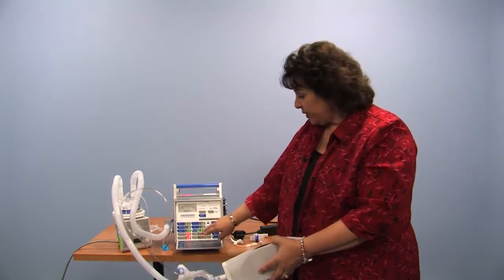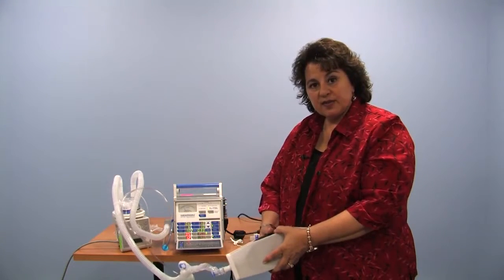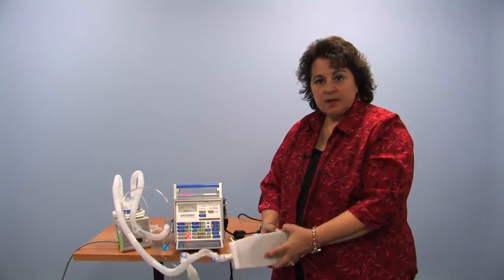I'd like you to know what the pressure, or the peak inhale pressure, the PIP, is for your child when the ventilator pushes in those 300 cc's. Let's, for example, say it's 20. Well, if tomorrow or the next day it's higher, why is it higher? Is there a blockage? Is the tracheostomy tube filling with some secretions? It's important to know if the machine's having a harder time blowing the same amount of air in.